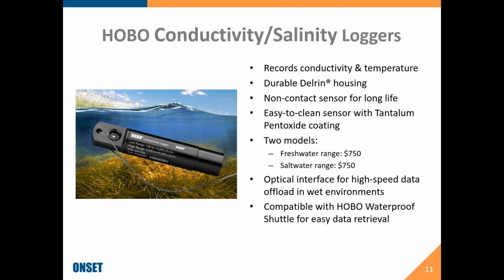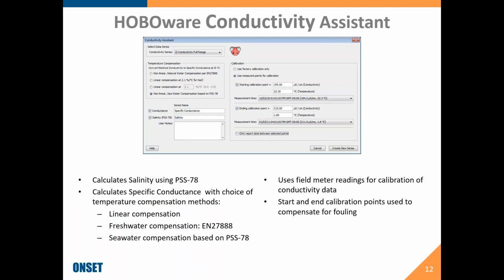It's also supported by the waterproof shuttle, which has a conductivity data assistant. This shows a screenshot from one of the fields in the conductivity data assistant, showing how it calculates salinity and specific conductance. You have to use start and end calibration points to compensate for fouling. This gives some guidance on how to complete these fields and get the end data for your conductivity measurements.